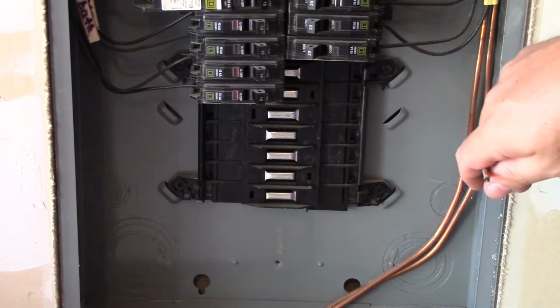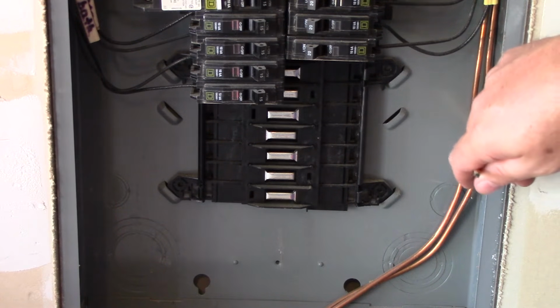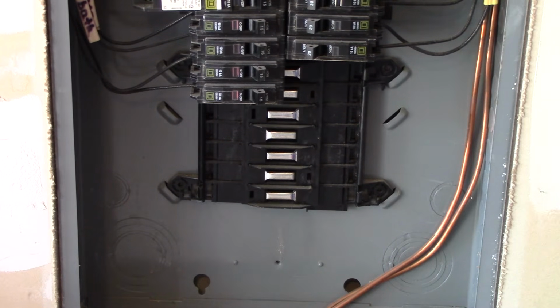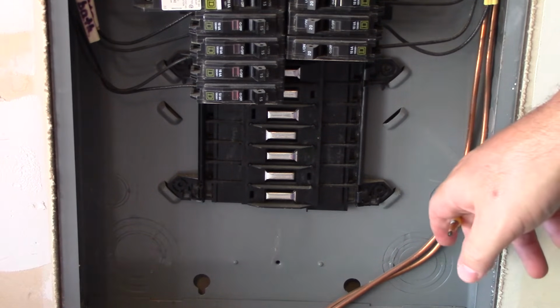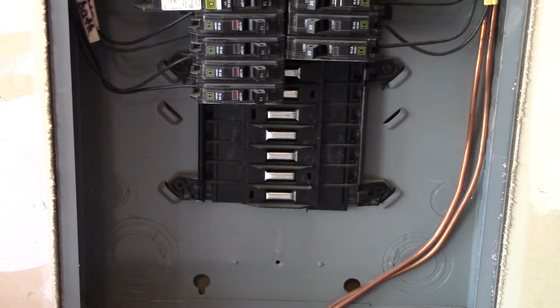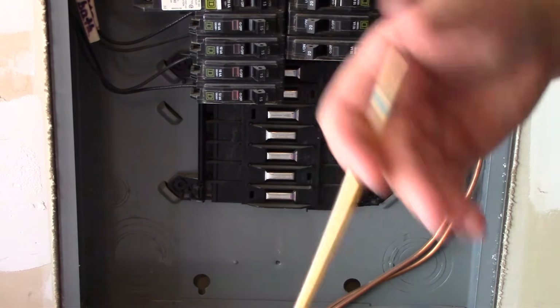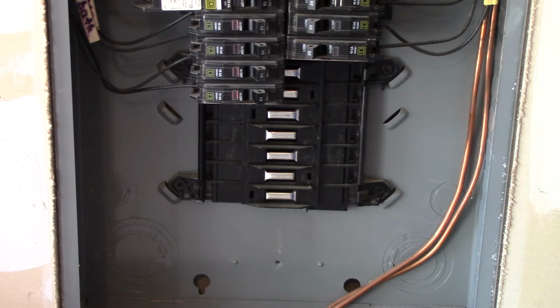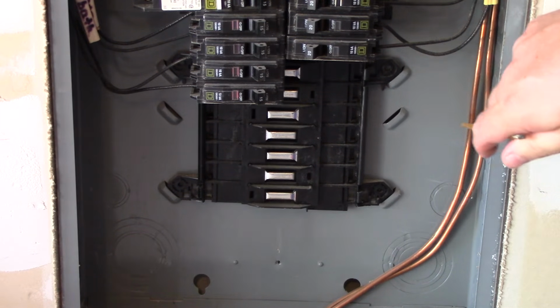All right, so anyway, we've got this application here. And they chose to use a 4-gauge copper solid as well for that electrode outside, the ground rod. They only needed a 6, but in this case they used a 4, probably all they had. So that was acceptable. Yes, it can be larger, provided that the lug that's on the actual electrode can handle the larger size conductor. Very frequently we have engineers who will go as high as a 4/0 to a ground rod, and we don't understand why they do that, except sometimes they believe it's more important around towers and things like that. But the reality is a ground rod can only handle so much. Okay, so you can go as large as you want, but the code doesn't require it to be any larger than a 6-gauge. Okay, so here they are.